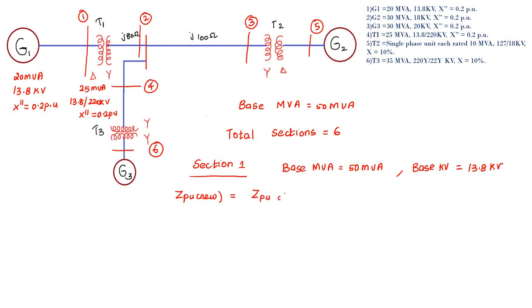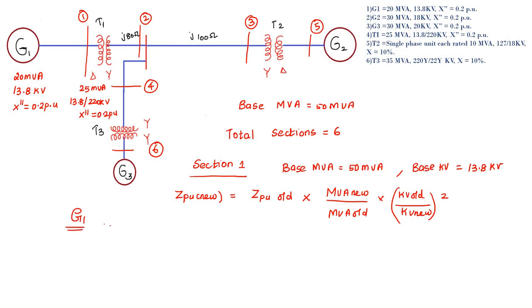Now I am going to find out ZPU new for the generator and transformer 1. The formula is: ZPU new = ZPU old × (MVA new / MVA old) × (KV old / KV new)². First I am going to find out ZPU new for generator 1. ZPU old is 0.2 per unit, MVA new is 50 MVA, MVA old is 20. KV old is 13.8 and KV new is also 13.8, so 13.8 divided by 13.8 the whole square.